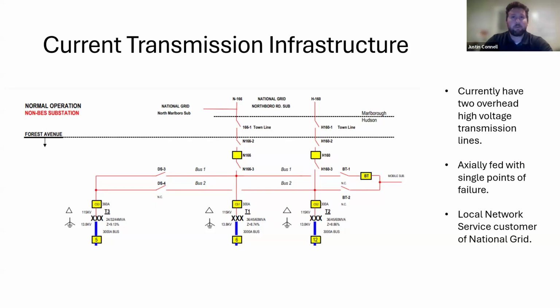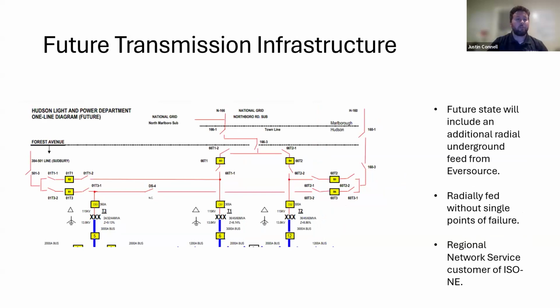Starting about 16 years ago, there was an idea called the Greater Boston Reliability Project, where an additional line was going to be brought in from Eversource to Hudson to backfeed National Grid and support the substation downstream, since there's generally a load pocket here. After a lot of permitting, legal issues, and general effort, things are finally coming to a head. We broke ground on this project and have landed a new underground high voltage transmission line that comes from the Eversource Sudbury station into Hudson.